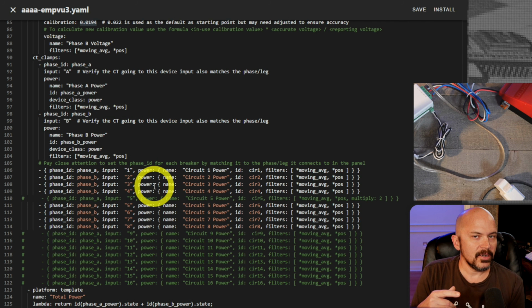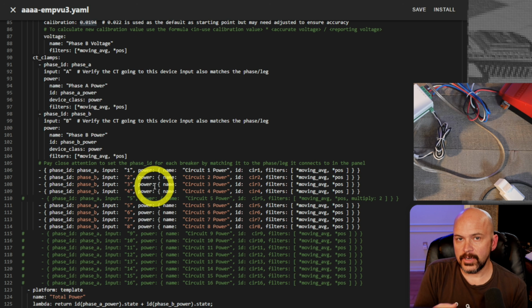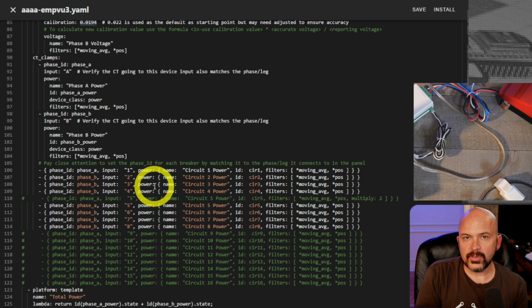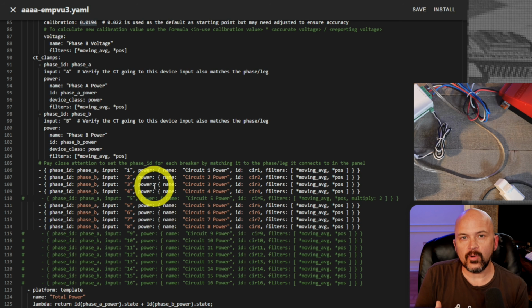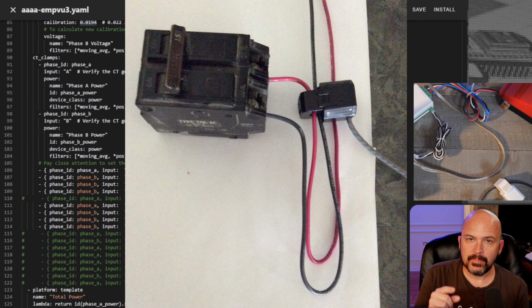Another thing to consider, like I talked about, especially in the US, say on your electric ovens and dryers, and other split phase 240 volt appliances - those are going to have the 2 hot legs. You can pass those through the same clamp, but you need to pass them through in opposite directions, kind of like shown here in this little picture. I have done it on some smaller loads. Make sure you're not going over the amperage of the actual clamp.